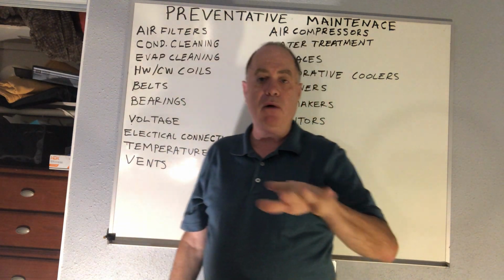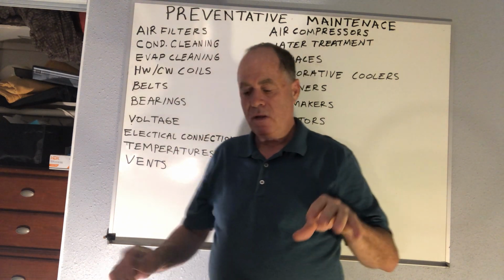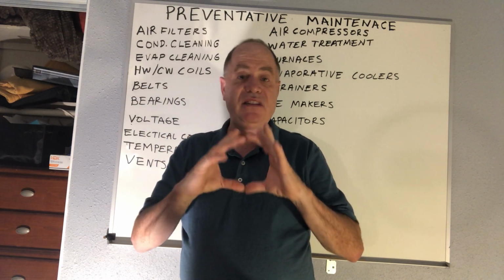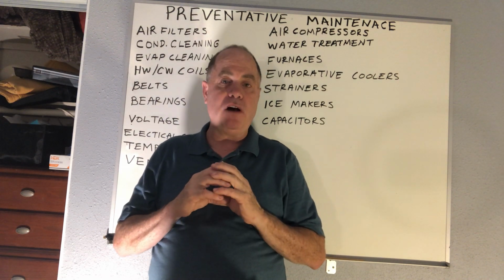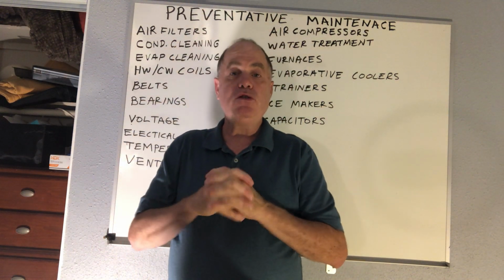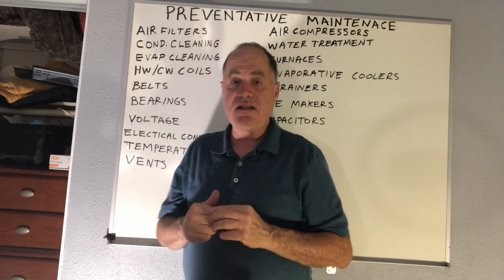These take grease. Now, a couple of general rules, and I recommend you setting a maintenance schedule that you can stick to where you're actually lubricating the bearings as needed. And here are some guidelines. All things equal, the oil is thinner, and if it's not a sealed bearing... Now, let me back up for one second. Manufacturers are tending to use sealed bearings more and more and more. In fact, on newer residential systems, it's almost hard to find any bearings that you can oil or grease. However, if you do have a bearing where you can oil it or grease it and pump grease with a grease gun into a grease fitting, also known as a Zerk fitting, these are bearings that need to be maintained.